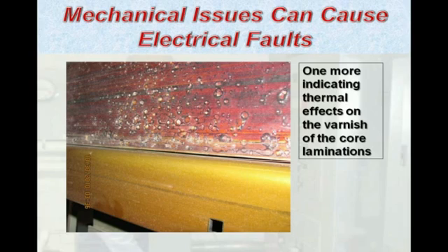Okay. I don't know if I asked this one. How did you handle the arc flash hazard when you were examining this unit? Yeah, the arc flash hazard analysis had been conducted at this facility, and for this particular unit, after employing some engineering mitigation, the hazard risk category was a number 3. The energy was reduced to about 24 cal per centimeter square, and the technicians dressed out in category 4 apparel just to err on the high side of caution.